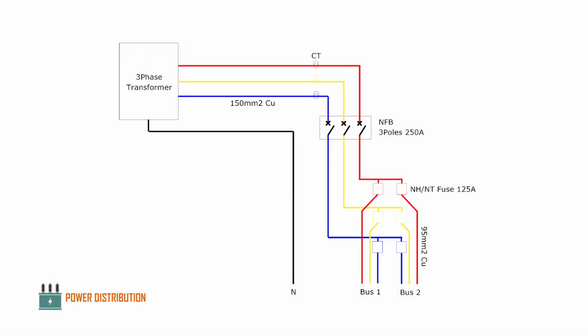Before we proceed to next video, let's take a look at the schematic diagram of this installation. First, we have the main power cable, which comes out directly from the secondary bushing of the three-phase transformer, which is 150mm squared copper wire or conductor. All of these three poles wire goes into a non-fuse breaker, or simply main breaker, rated for 250 amps, and there are current transformer in between to measure the current flowing out of the transformer.